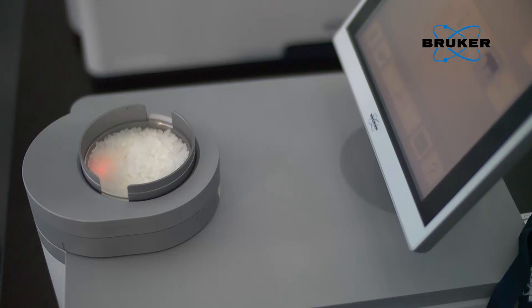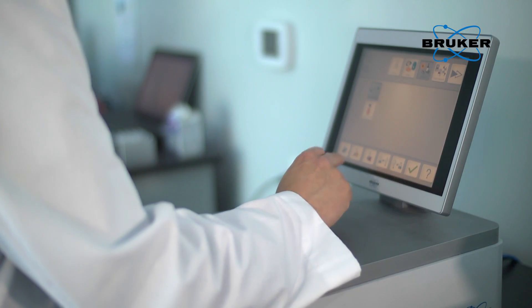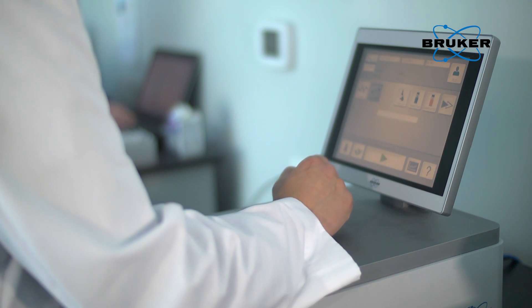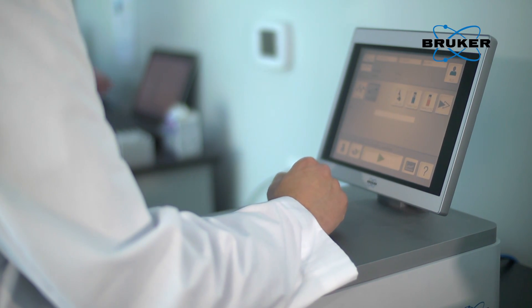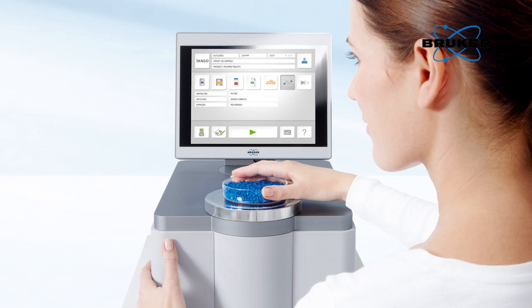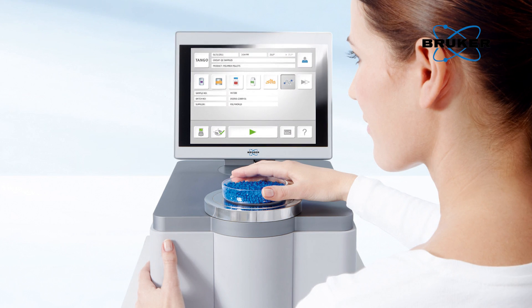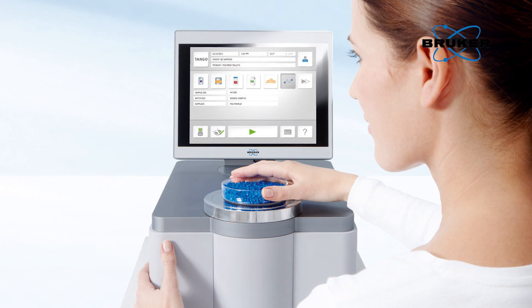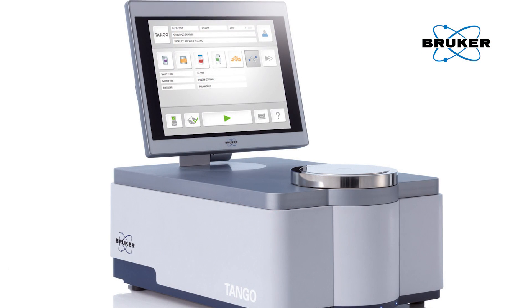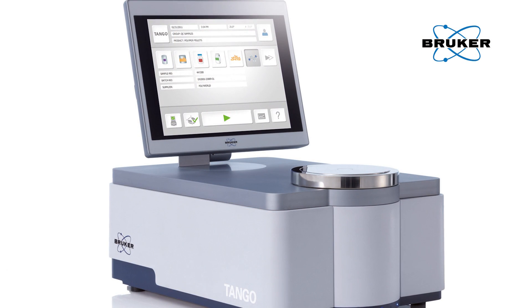In addition, you also have the calibrations that you develop for that particular material. The methods, or the calibrations that you have on the Tango, can be qualitative or quantitative, or both. This is a big advantage of the Tango software, allowing for multi-evaluation predictions. The calibrations can be set up to identify your materials, as well as give multiple component evaluation, all from the same scan.